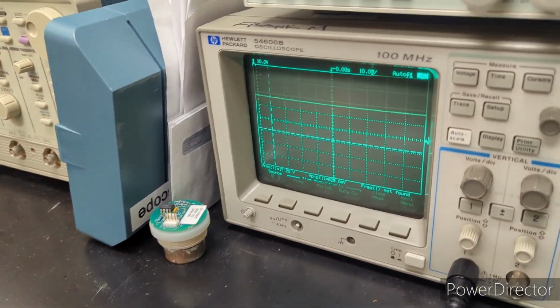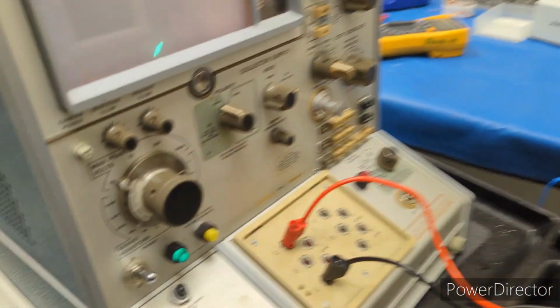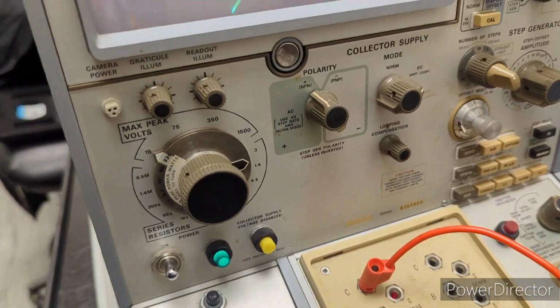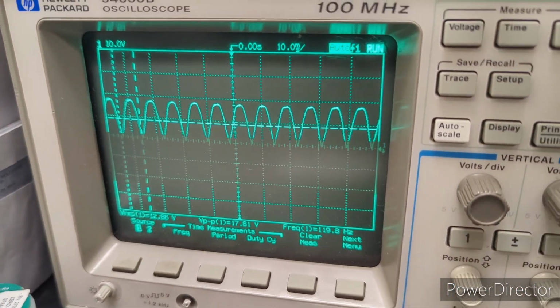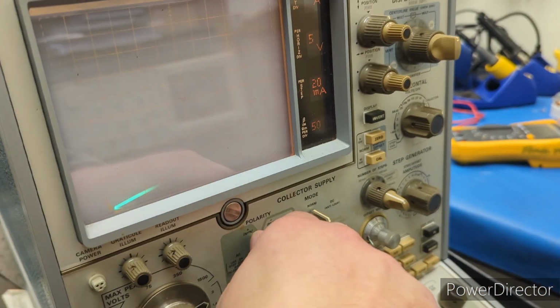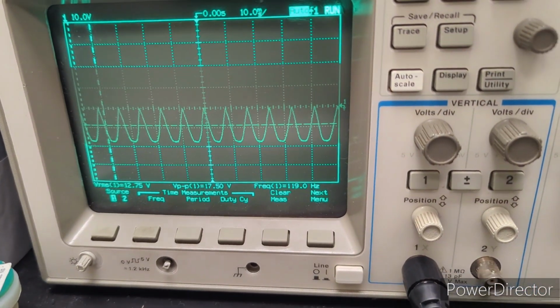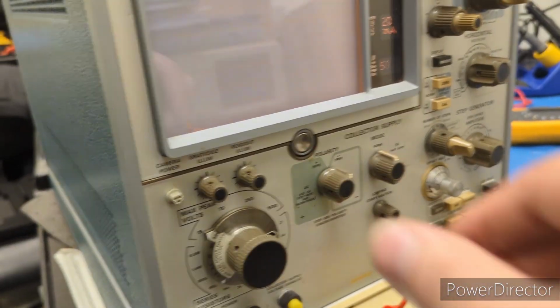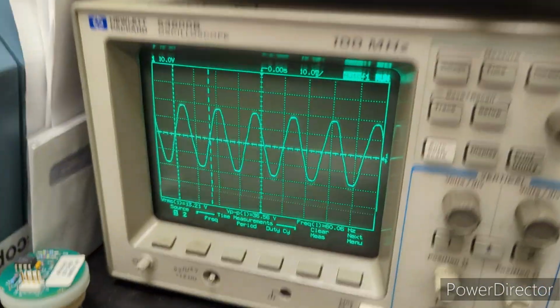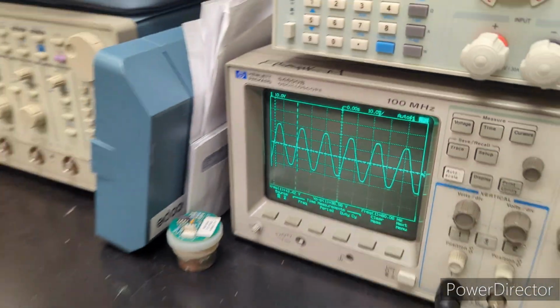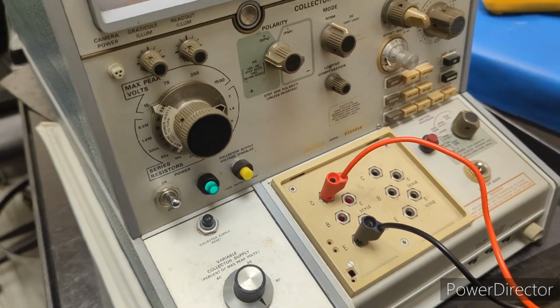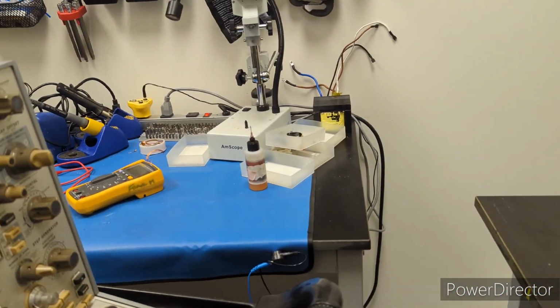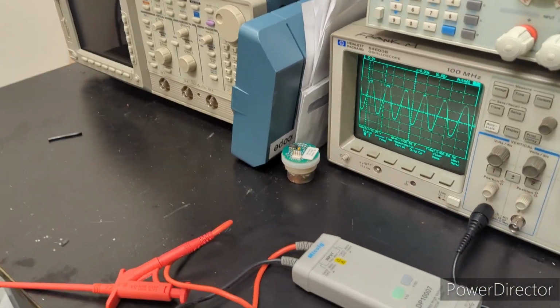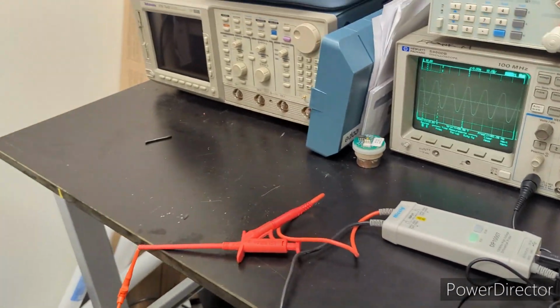I also have to check the manual to see if there's a spec for this collector supply as well. But it's a much different situation than the other supply voltages. If we put it in normal mode, that's your fully rectified sine wave, and then PNP flips the sine wave. And then if we put it into AC, there you go. So not really seeing any issues there with the collector supply. That's good. I'm glad to see that. And the collector supply voltage is a completely different source than those voltages we were checking earlier. It's a different transformer, so it's a completely different circuit. But it's good that this is looking a lot better.